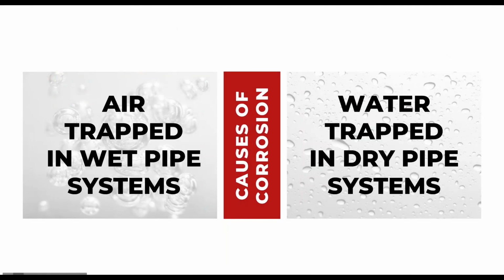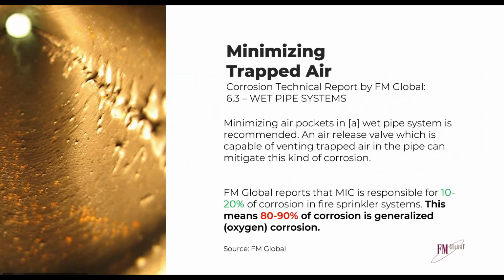So we know that if we can get air out of a wet system, we can cut down on corrosion. The same way, if we can get water out of a dry system, we cut down on corrosion. We're reducing one of those three. If we can reduce the air, the steel, or the water, then we are affecting corrosion.